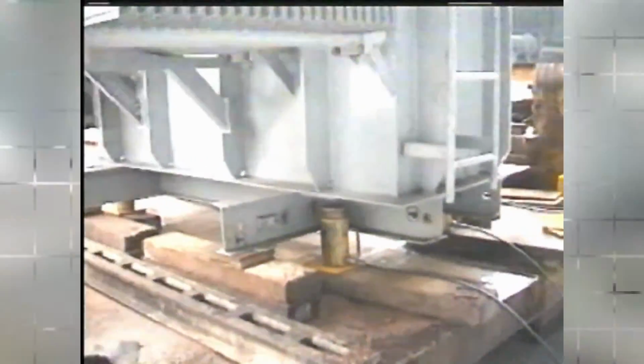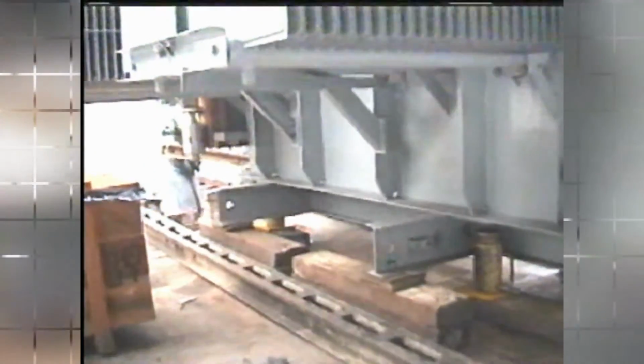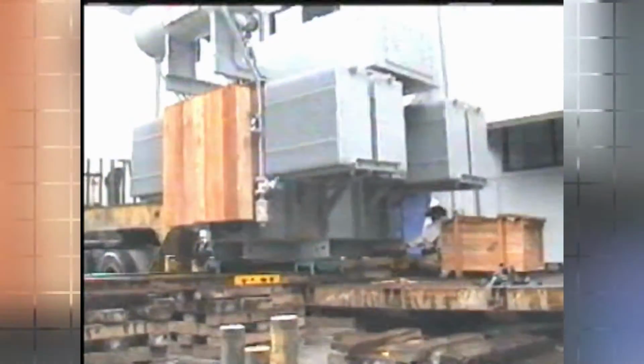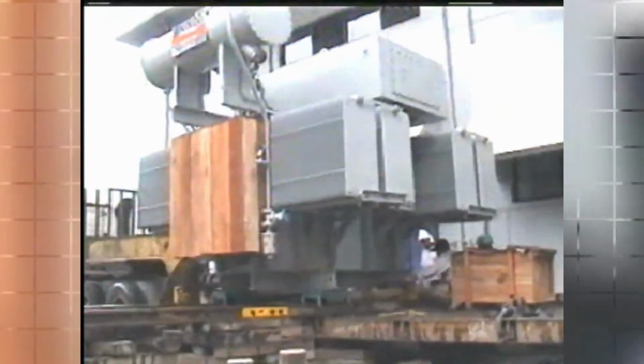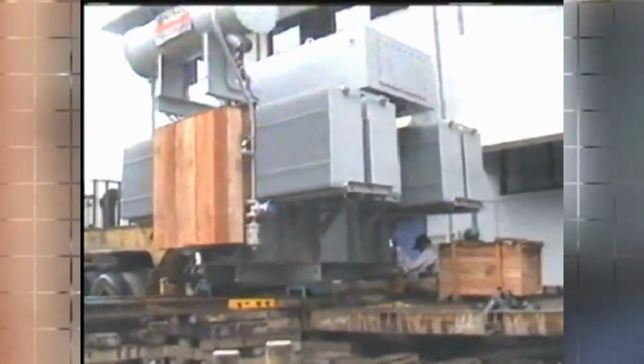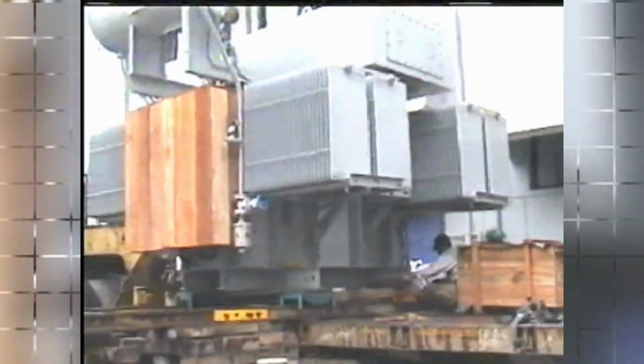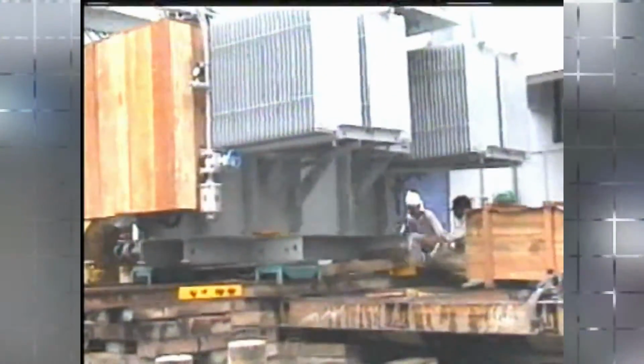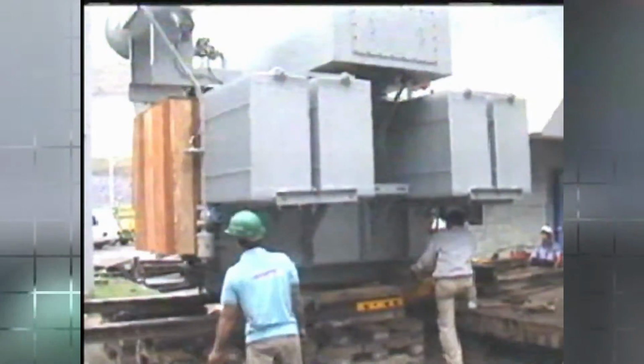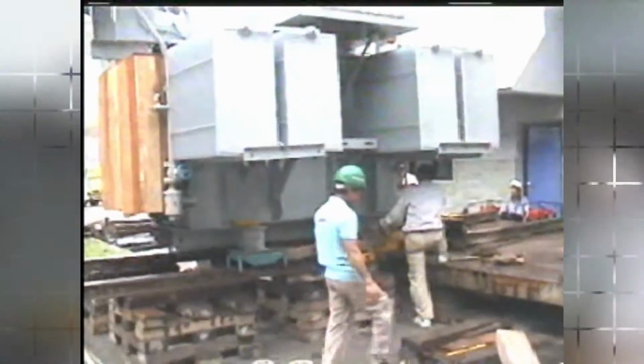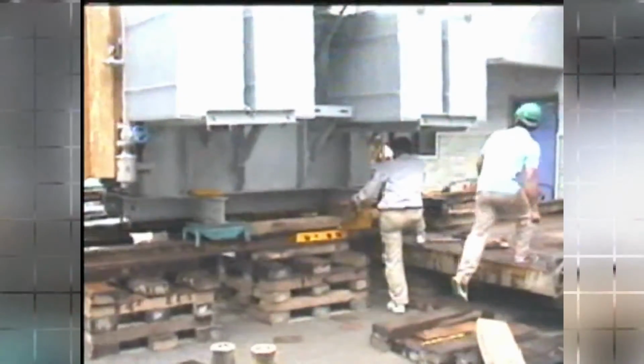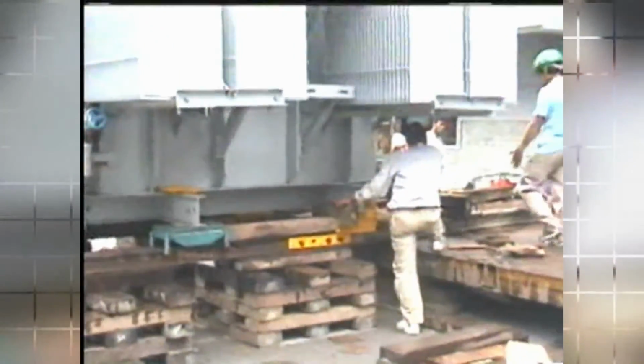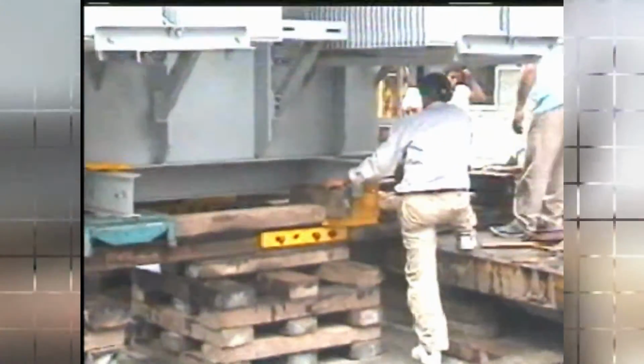The transformer is designed for a frequency of 50 Hz. The continuous rated power of both windings of the main transformer is 7,000 kilovolt-amperes under natural oil circulation and natural air cooling operation at any tappings. A shock recorder is fitted on top of the transformer's tank to monitor any rough handling which might cause the transformer to be damaged.